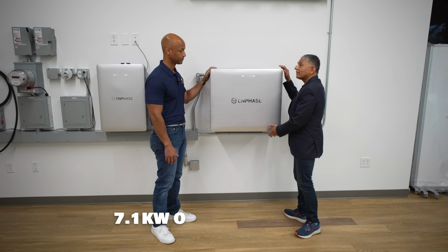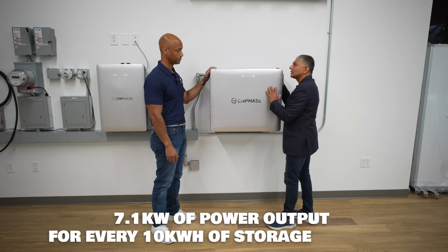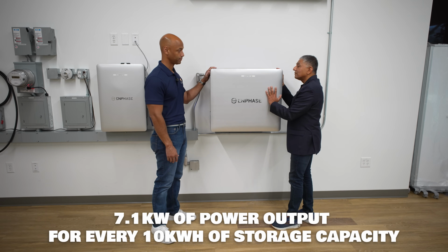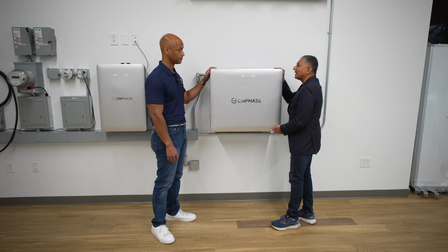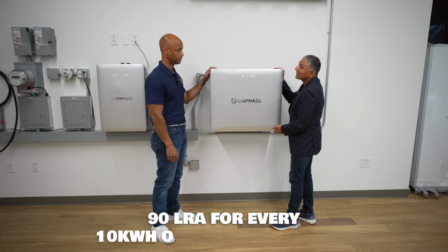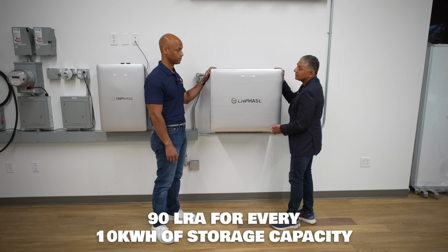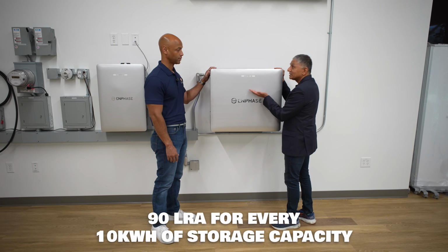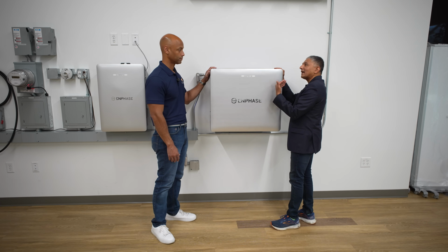So, to summarize capacity: in terms of power output, for every 10 kilowatt hours you get 7.1 kilowatts of power. But the more important characteristic is that it's got a 90 amp LRA. For every 10 kilowatt hours, you get 90 amps of locked rotor amps, which is a critical unit to start air conditioners.